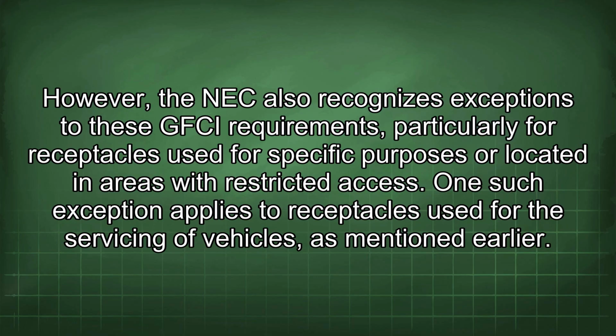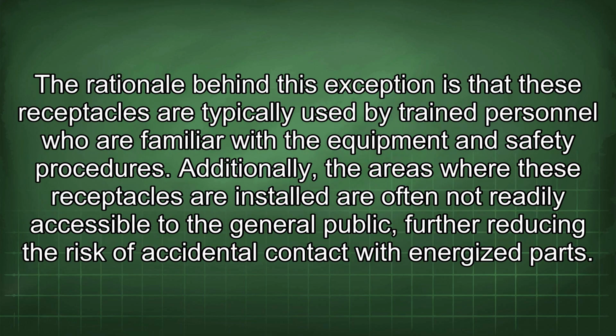However, the NEC also recognizes exceptions to these GFCI requirements, particularly for receptacles used for specific purposes or located in areas with restricted access. One such exception applies to receptacles used for the servicing of vehicles, as mentioned earlier. The rationale behind this exception is that these receptacles are typically used by trained personnel who are familiar with the equipment and safety procedures. Additionally, the areas where these receptacles are installed are often not readily accessible to the general public, further reducing the risk of accidental contact with energized parts.